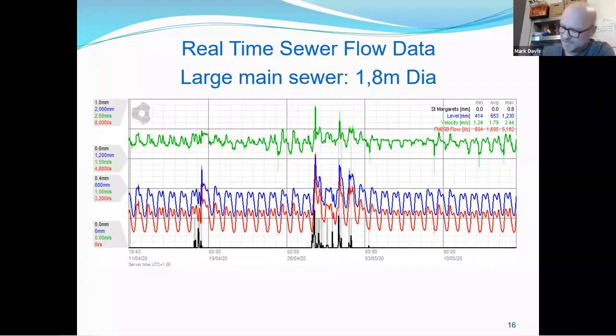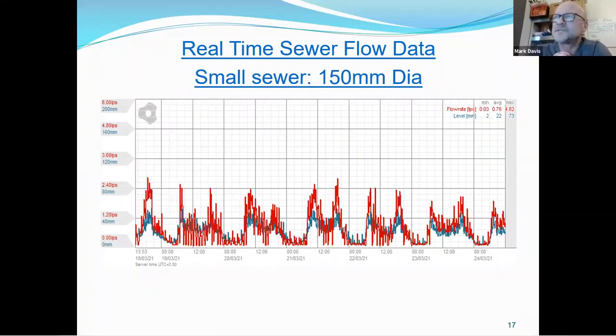I mentioned needing a wide range. That's important because we can also use the same equipment to measure low flows. And here you can see we're measuring levels down to 2 millimeters, effectively a trickle, up to 73 millimeters in a very small pipe for a very small local sewer network. The importance of being able to measure these small flows is that you can pick up leakage and infiltration, even when you shouldn't have any flow. It's very useful.